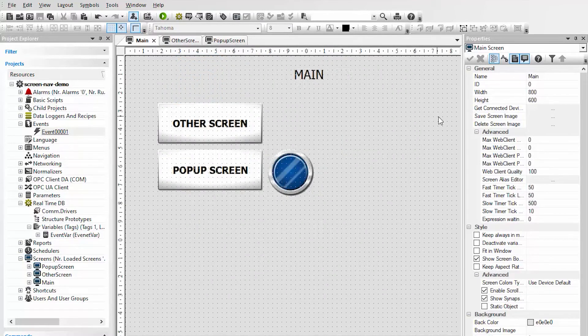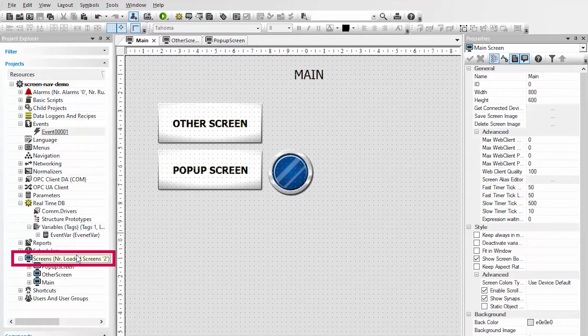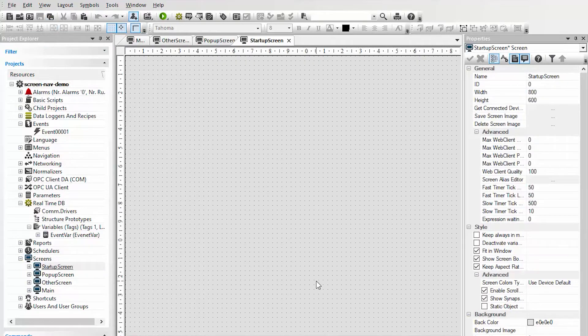Next I will demonstrate how to select a startup screen. Without defining a startup screen, when the HMI project is deployed to an HMI device the project will not know where to start. In our simulation mode up until this point the simulation simply starts with the screen that is displayed. However if this was deployed to a device the project would not start. I am going to create a special startup screen — I could just simply use my main screen but I will call this startup screen. Often times startup screens are used to display a company logo and contact information for the OEM of a machine.